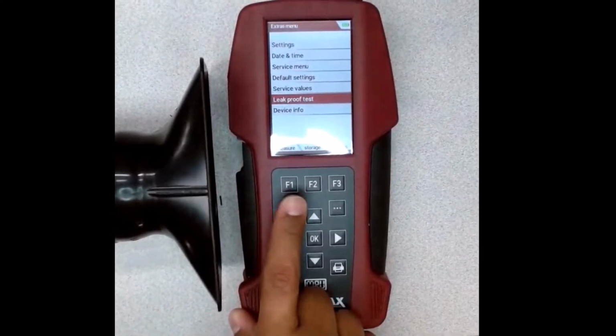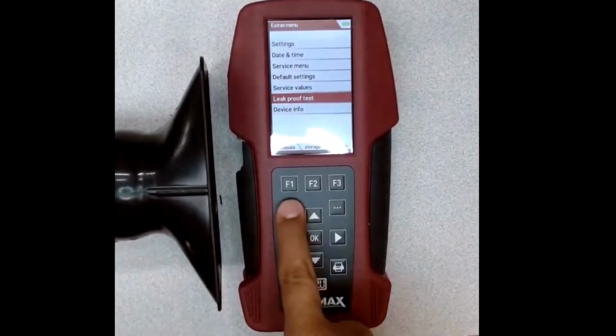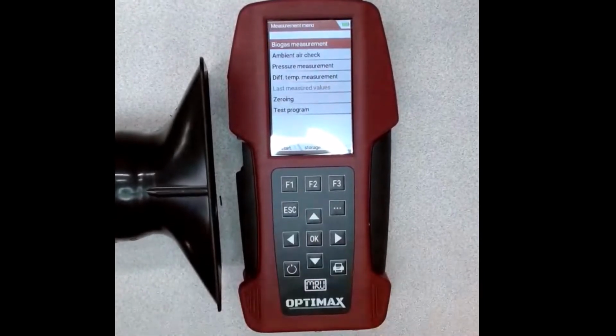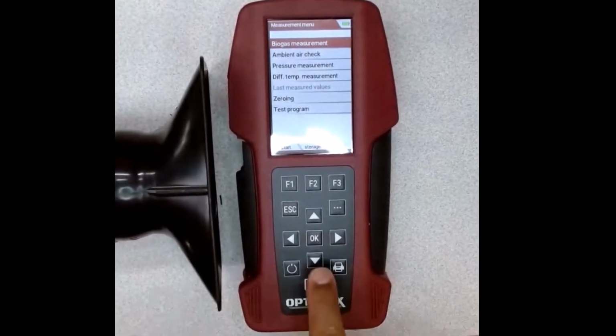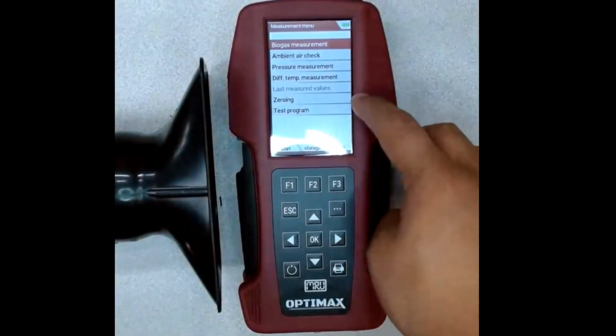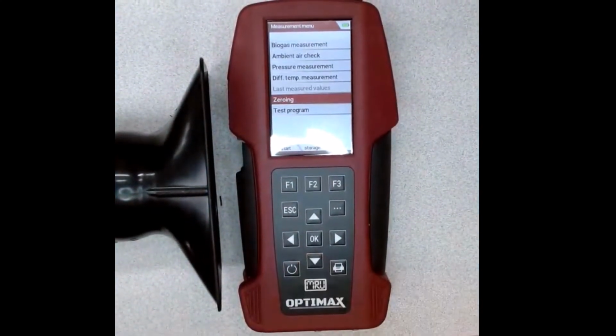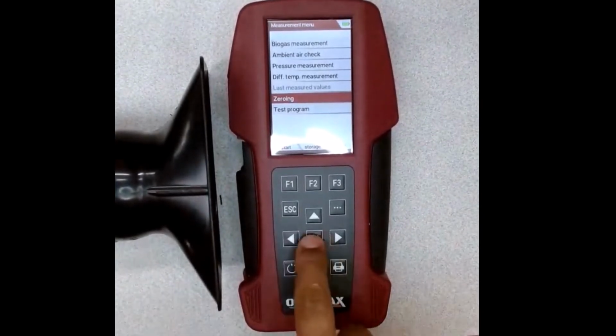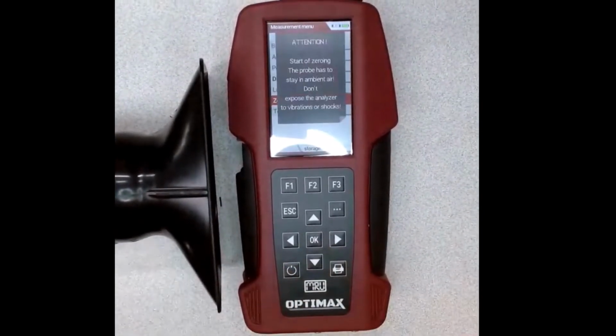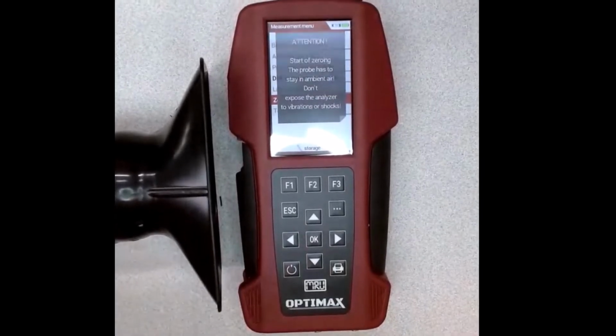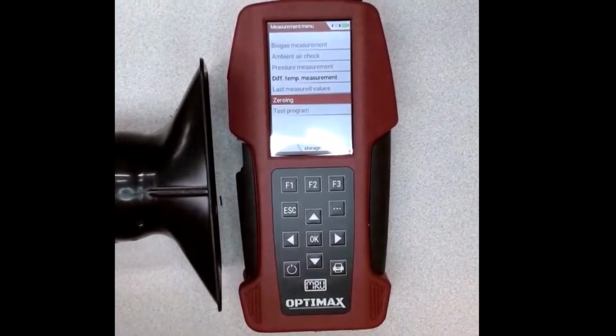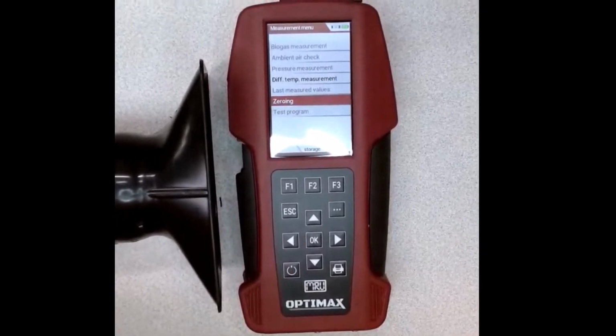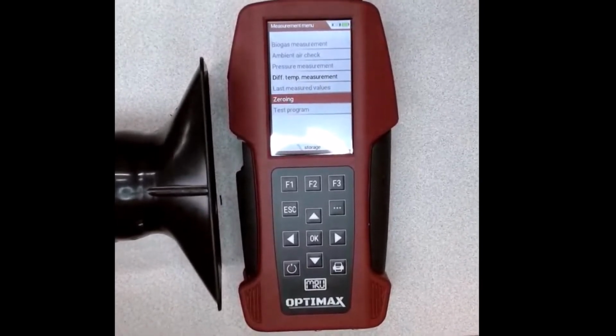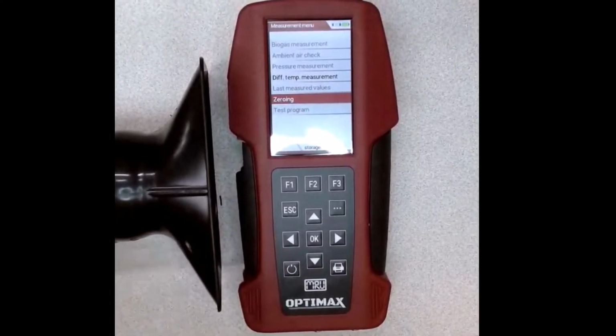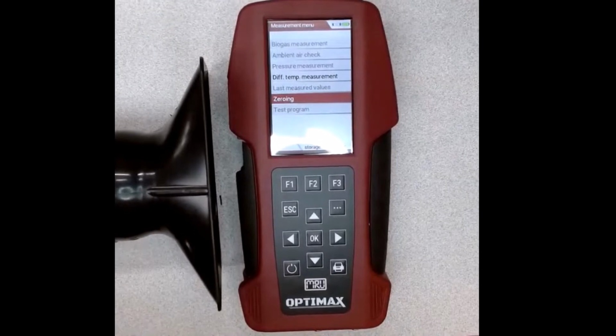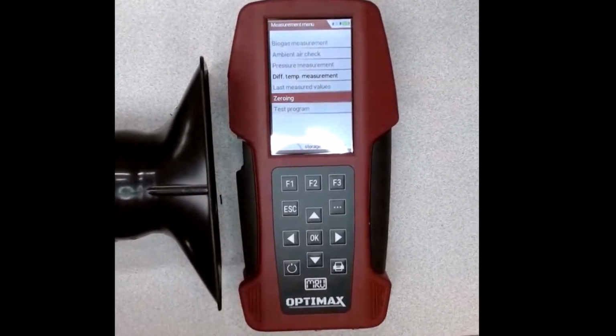But then after the leak proof test, we'll escape again to the main menu. And we'll navigate down to zeroing. And then we'll select that. So after the fresh air purge and then the leak proof test, we run a zero. So you've purged the whole analyzer with fresh air. So now we run a zero so that it calibrates to fresh air values.